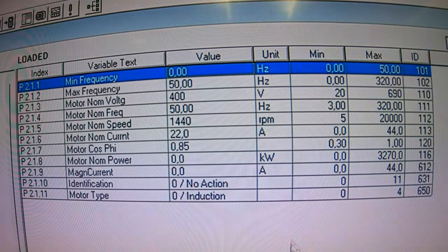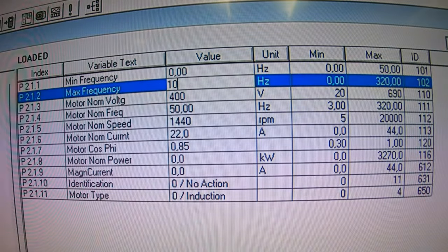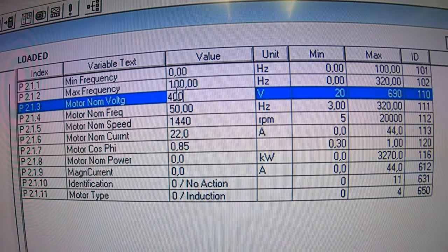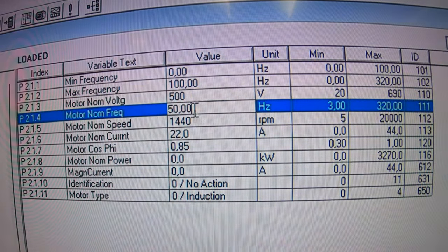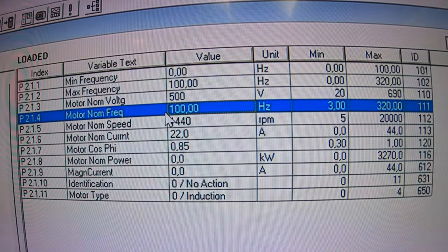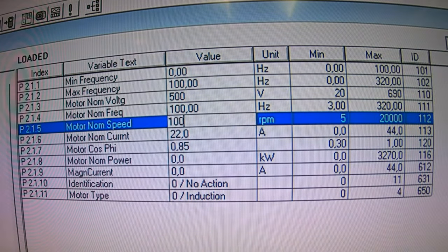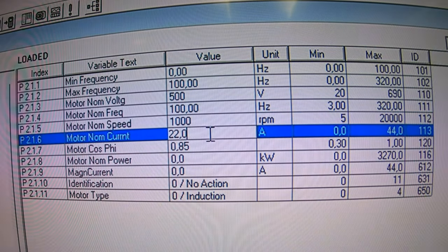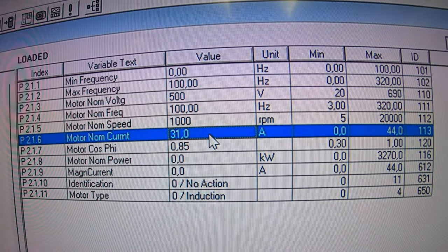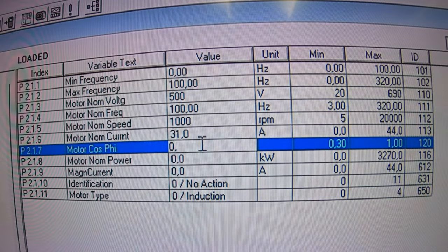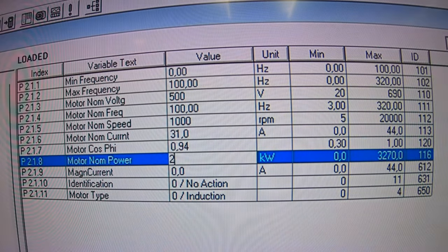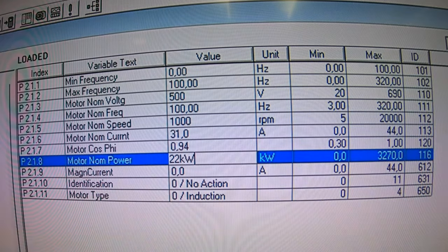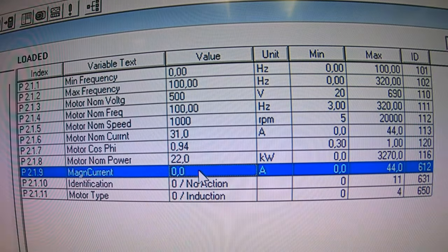For my specific motor, I select these basic parameters. I start with 100 Hertz for the maximum frequency because that is my motor nominal. 500 volt and it hits 500 volt at 100 Hertz. This gives the motor back EMF curve. 1000 RPM nominal at 100 Hertz. This gives that is a six pole motor. Nominal current of this motor is 31 ampere. Nominal power is 22 kilowatts. Do I need 22 kilowatt for doing the tuning? No. Tuning can be done at quite lower kilowatts.